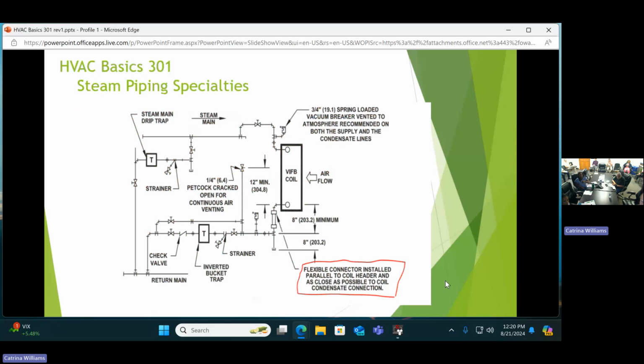These are the flex connector. This is a bottom float on a vertical coil. The bottom header is a floating header. So the top one's stationary, bolted in. The bottom one is floating because fin tubes, being made out of copper, when you hit them with 250 degree steam, will grow in length. So that flex connector is very important. It takes up that growth in length of those tubes while they're hot. So the trap, we're showing an inverted bucket trap. On other steam systems, we also use what's called an F&T trap. I'm not going to get into how traps work, but I'd be glad to give you that as a separate class someday.